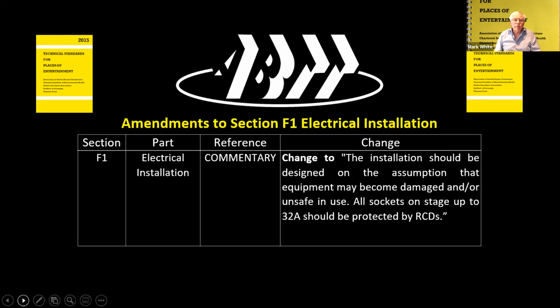There's been a lot of emphasis on RCDs for the last 10 years at least, to the point where the various regulations and requirements change, so that we currently say in F1 that we assume it's going to become damaged in use. We assume that it's going to require inspection and testing every so often, and that all the sockets on the stage up to 32 amps shall be protected by RCDs.